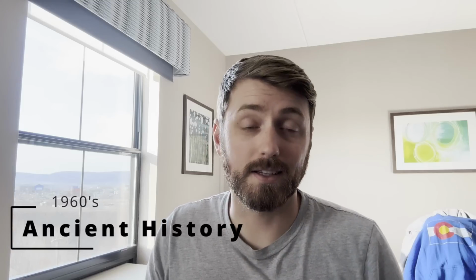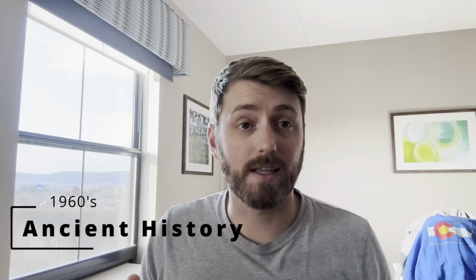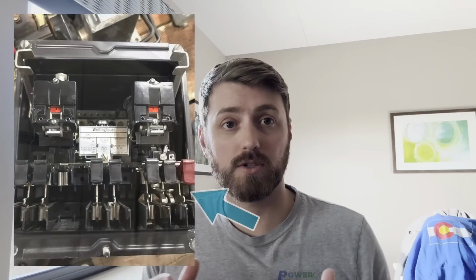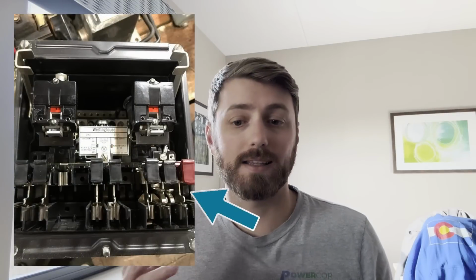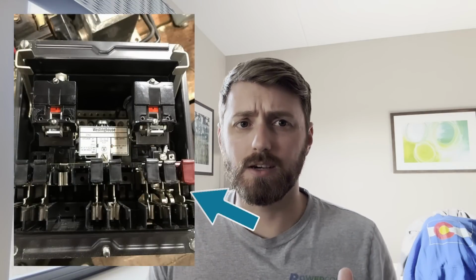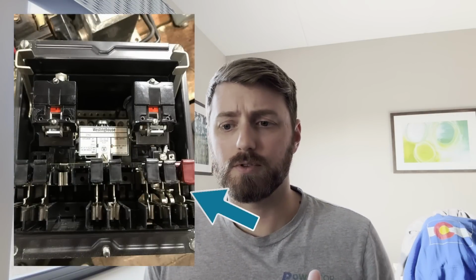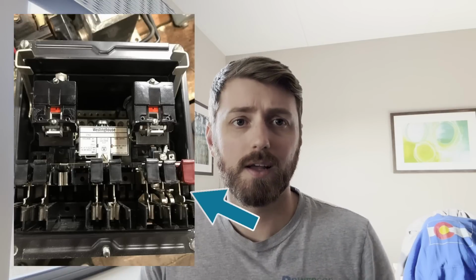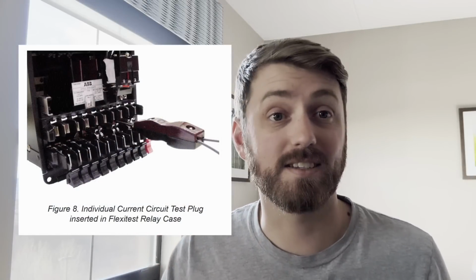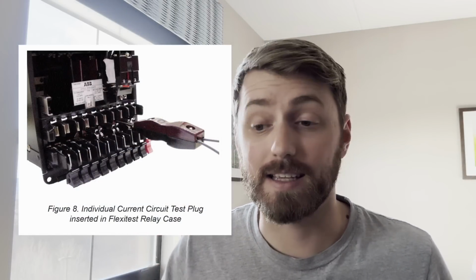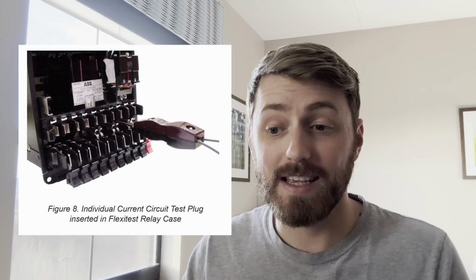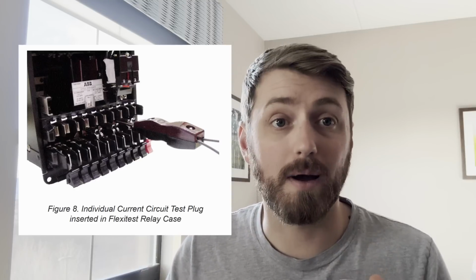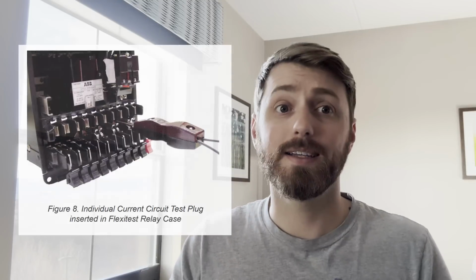Westinghouse started making electromechanical protection relays with the Flexitest switch system back in the 1960s. Now, I'm not sure if the CO relay was one of the first ones to have them, but obviously they were a huge improvement at the time. We could conveniently isolate and test the relays in the field inside the case. The FT cases quickly became incredibly popular and stayed popular for decades.